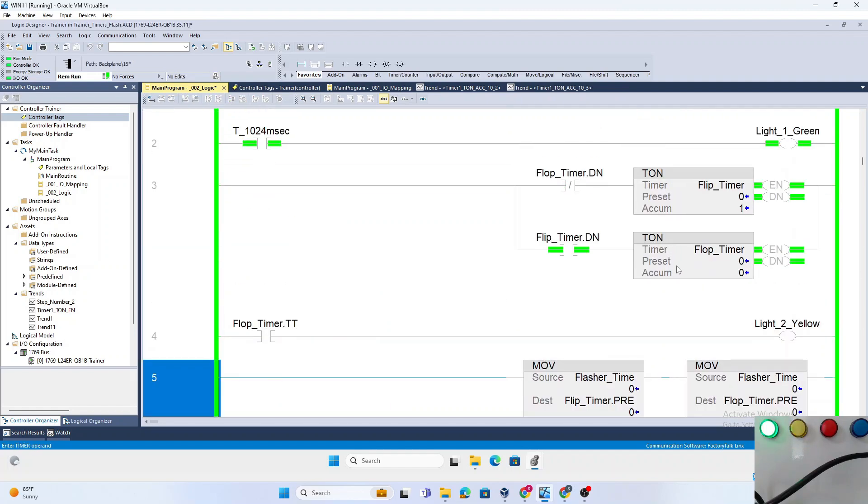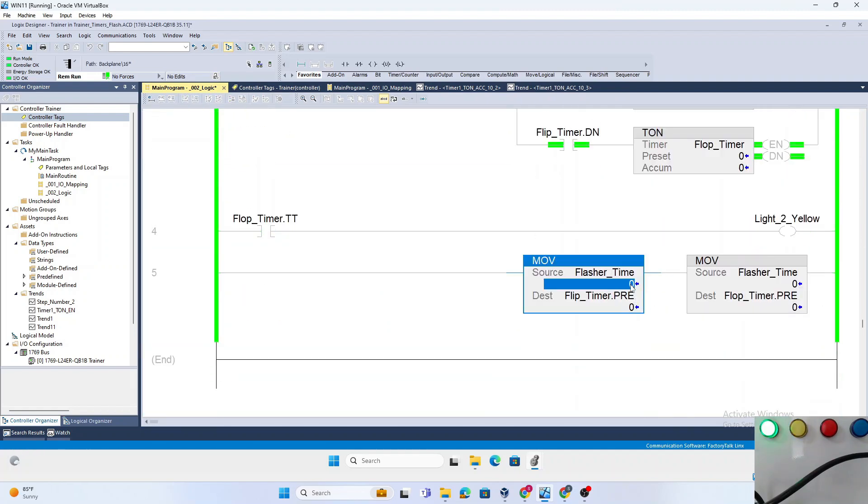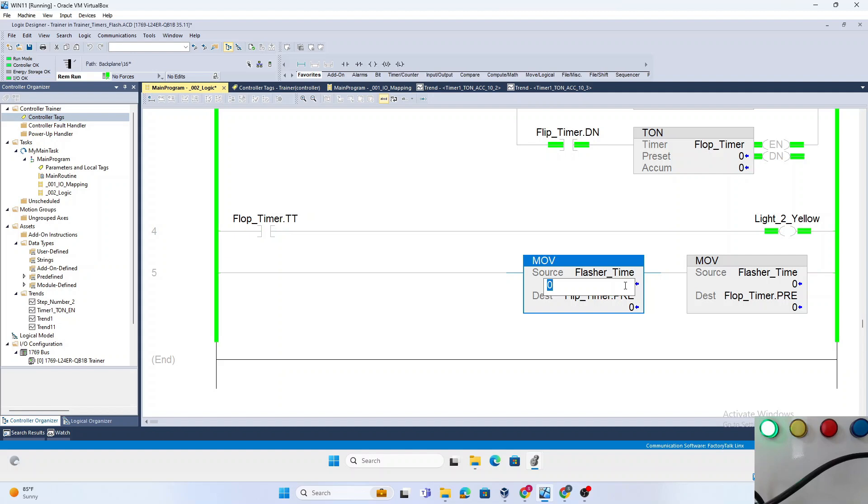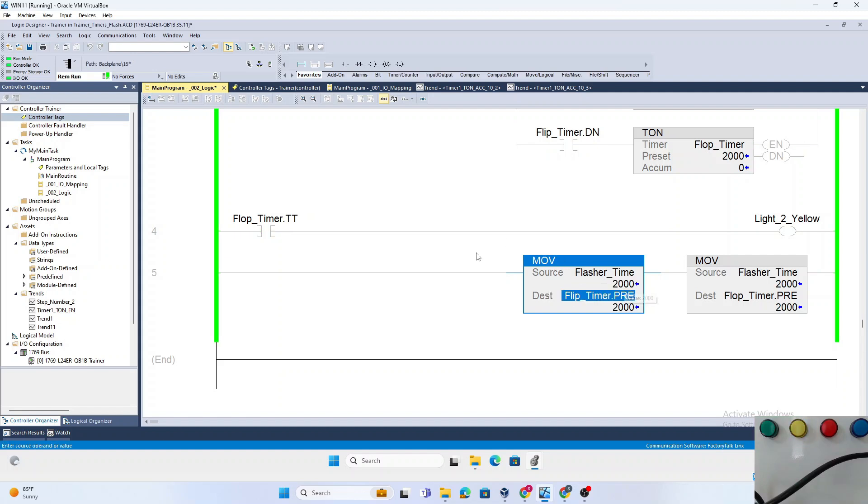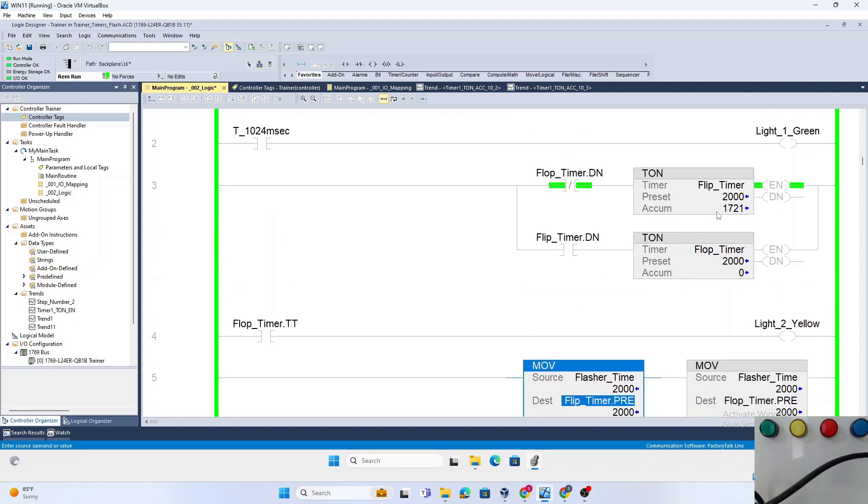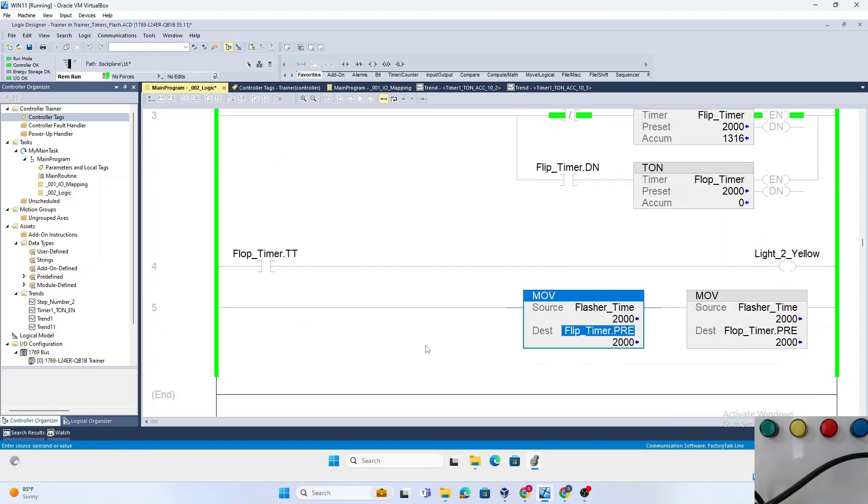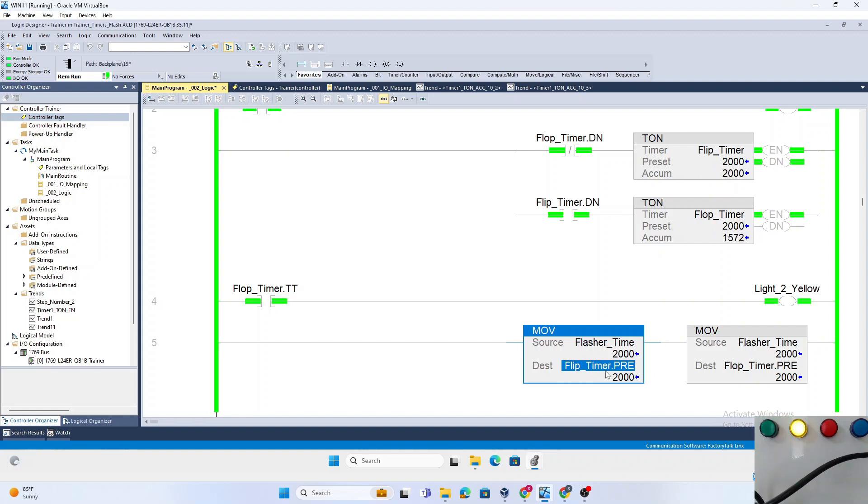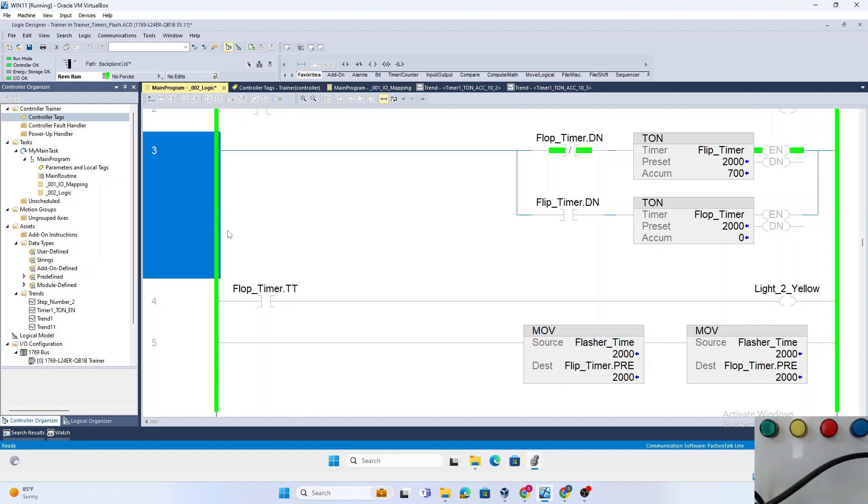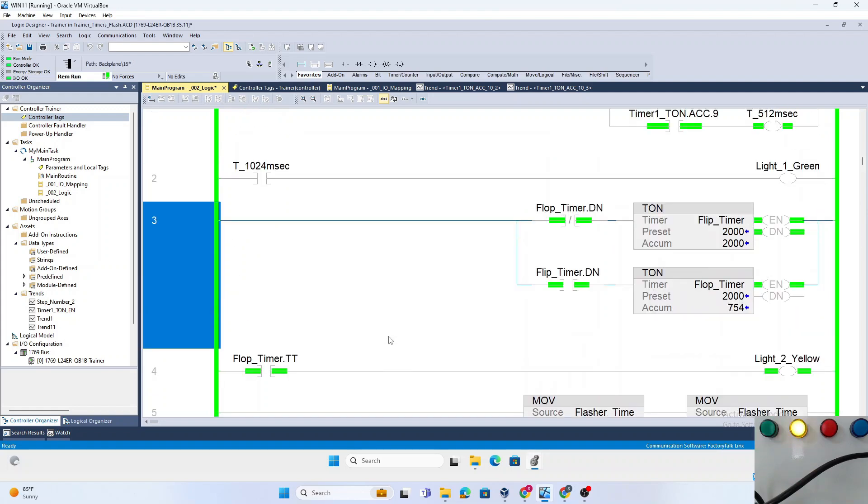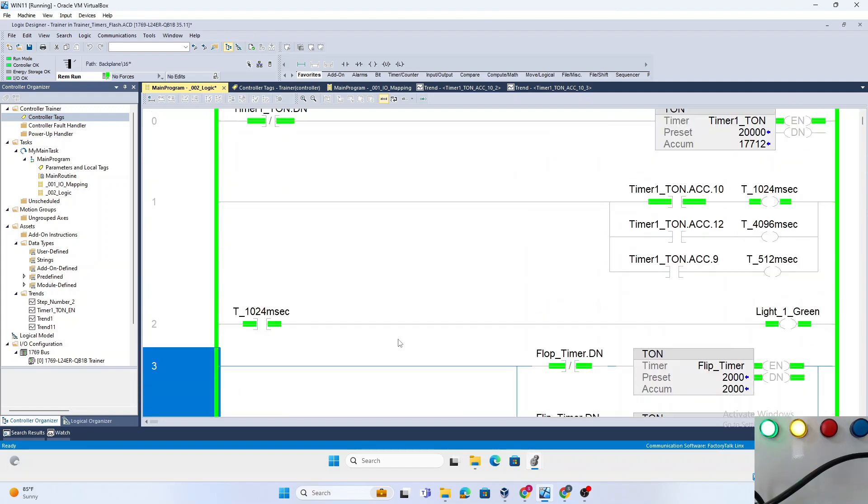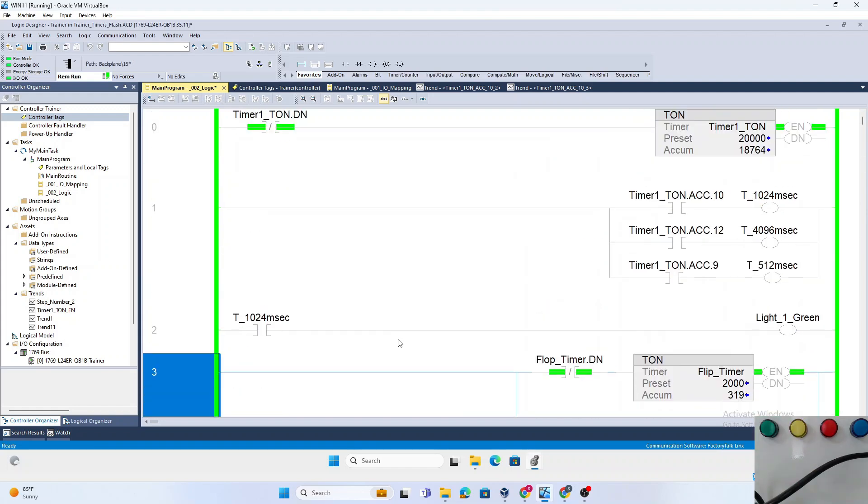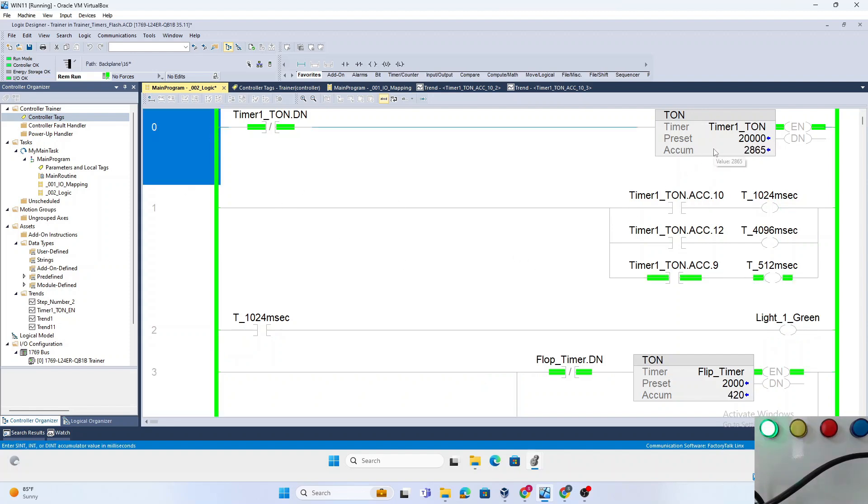And then we just type 2000, and now we have a two-second timer. That's the second method. The second method involves creating two timers and having a move instruction, so it's about three rungs. If you like this way, this is perfectly fine. If you don't want to create multiple timers and just have one timer, method one is the way.